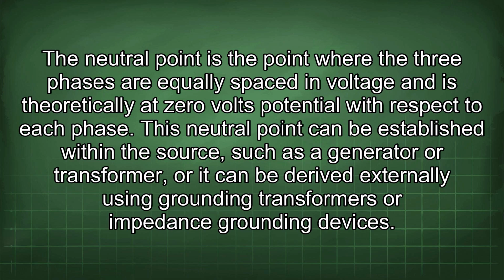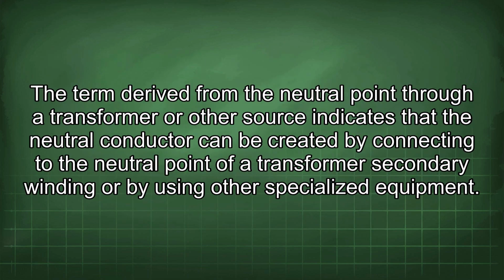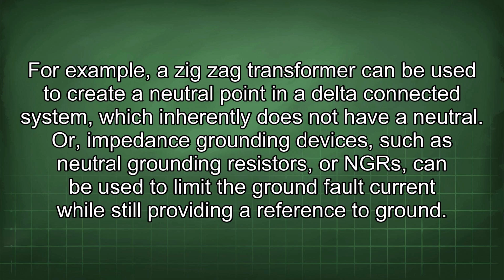This neutral point can be established within the source, such as a generator or transformer, or it can be derived externally using grounding transformers or impedance grounding devices. The term derived from the neutral point through a transformer or other source indicates that the neutral conductor can be created by connecting to the neutral point of a transformer secondary winding or by using other specialized equipment. For example, a zigzag transformer can be used to create a neutral point in a delta-connected system, which inherently does not have a neutral. Or impedance grounding devices, such as neutral grounding resistors, or NGRs, can be used to limit the ground fault current while still providing a reference to ground.